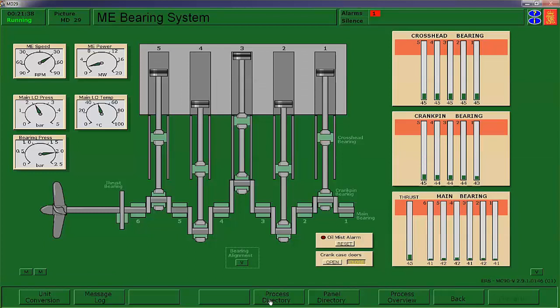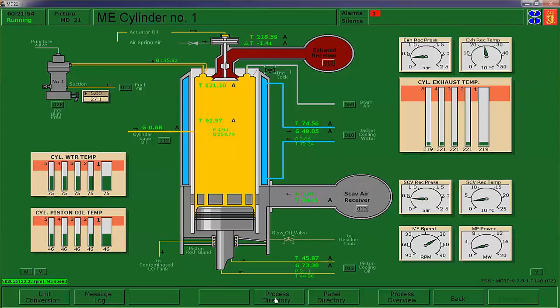Another very, very important thing is that you are watching your exhaust temps and making sure that they're fairly similar in temperature, that there's not any big deviation, and they're not up through the alarm point. The alarm point is about 450 degrees C. So we're down in the 200s. So we're good.